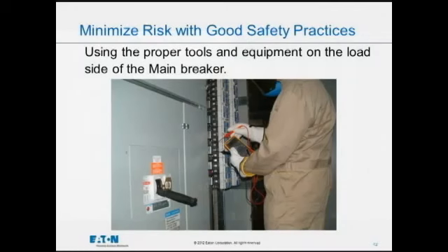So working on the line side of a device, or in the same cell as the line side connections, is a place where the hazard is generally high. And as we move away from that, we start to get relief in faster and faster operating speeds, which allows us to wear less protection and makes it easier to do the job.